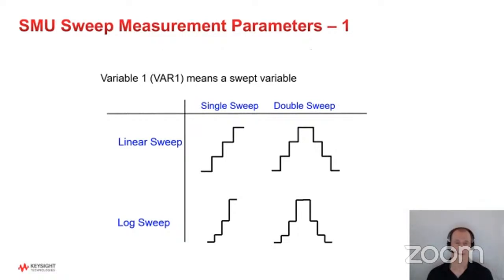There's a bunch of different parameters you can also define when you're making a sweep measurement with an SMU. Showing some of the key ones here. Typically, you can do either what's called a linear sweep, where the points are, as the name implies, equally spaced and linearly, or you can also do a logarithmic sweep, where they're spaced equally in a logarithmic sense. And we can do both single and double sweeps on our SMUs. And again, there are different reasons you might want to do both of these. Also want to mention that you might sometimes see this term var1, especially in our older instruments. That just means variable 1, and it means the sweep variable. It's just the terminology for the older products. The newer products just say sweep.